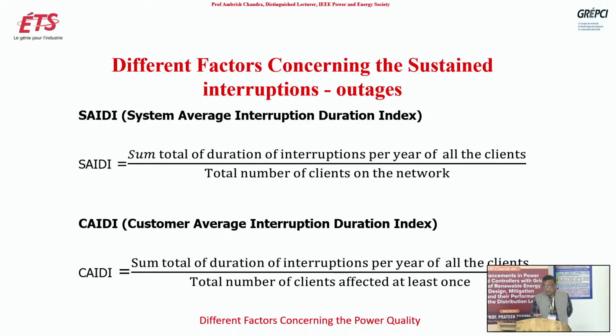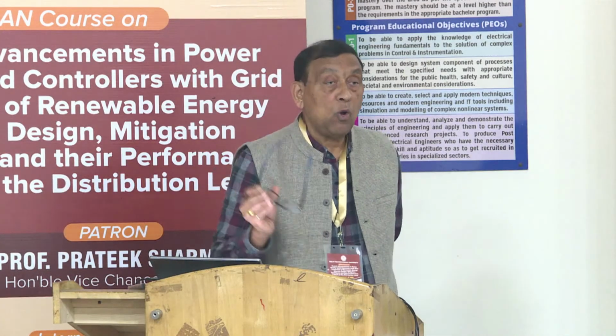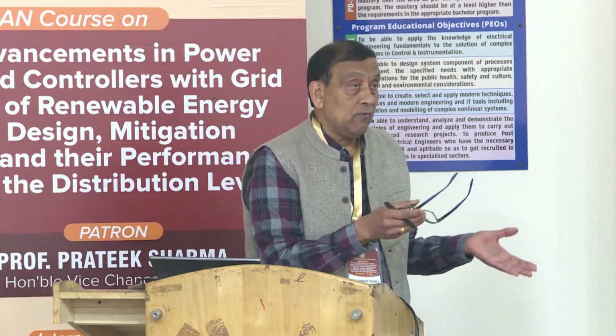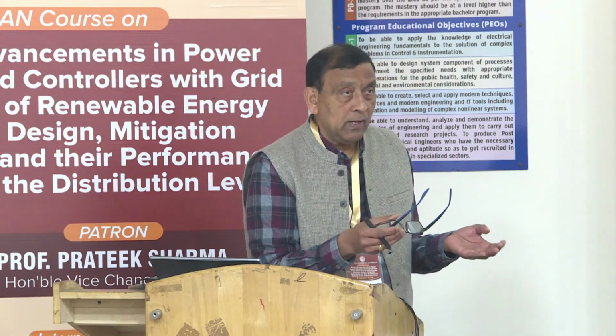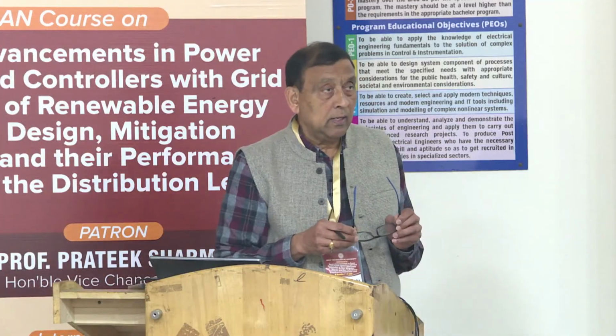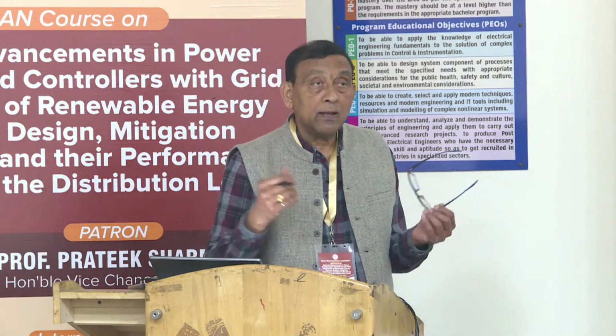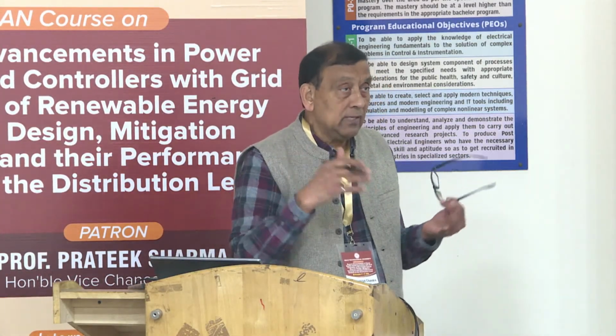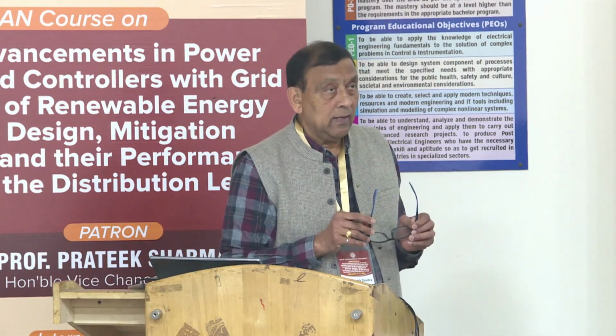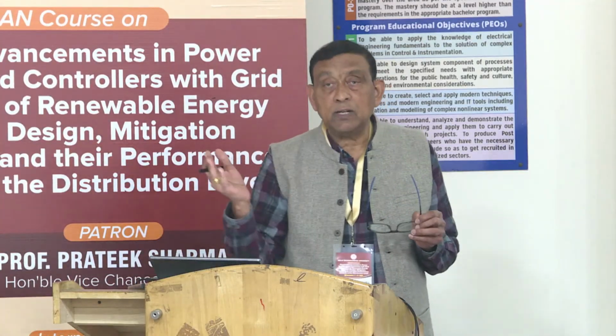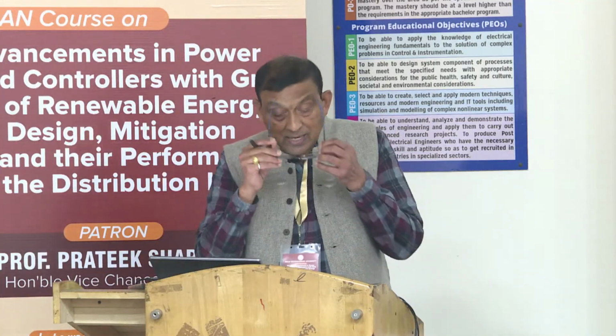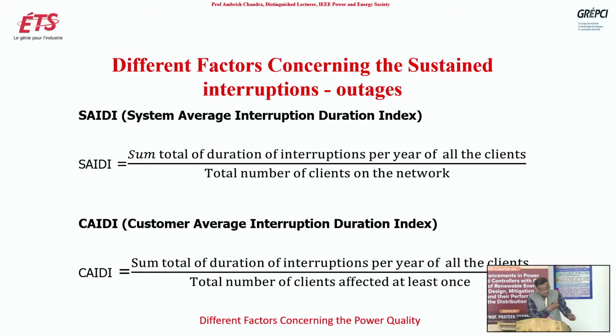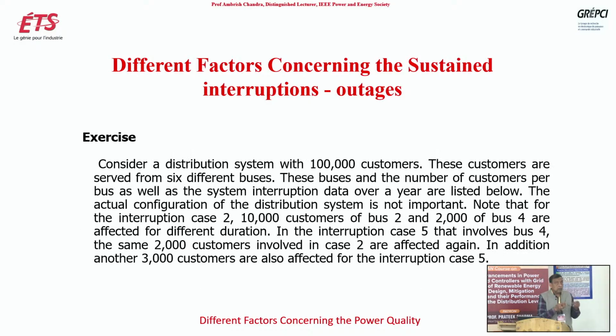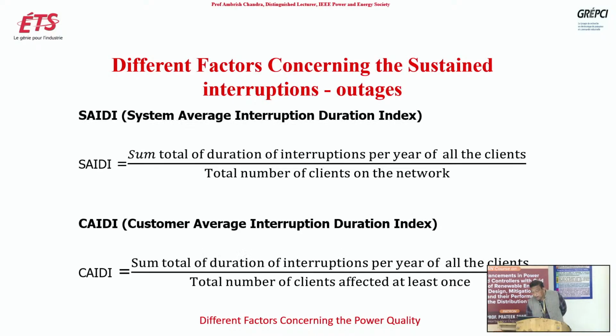So basically, SAIDI and CAIDI are about the duration, how long the system was down. It means a technician was on the site to see the problem and was trying to correct it, for example the transformer. Perhaps the technician took a long time to repair the transformer. If the technician is taking a long time, it means he has not been properly trained. So he should be trained for the maintenance work, right? So this is the duration, and the frequency is different. This is the difference between SAIDI, CAIDI and SAIFI, CAIFI. There's a numerical question, but we don't have time for it. But yeah, no, they cannot be equal because you see, total number of clients affected at least once.